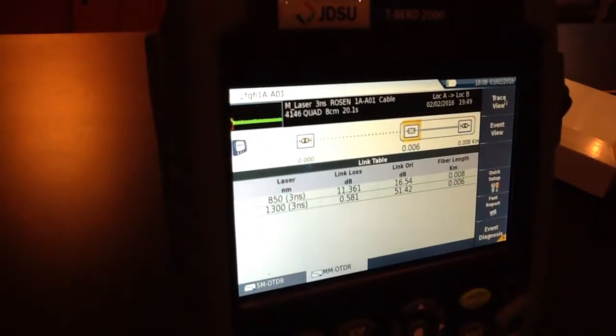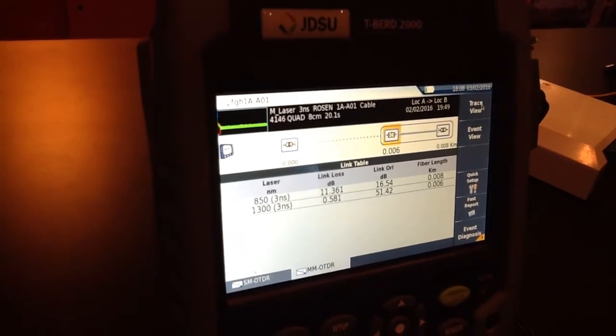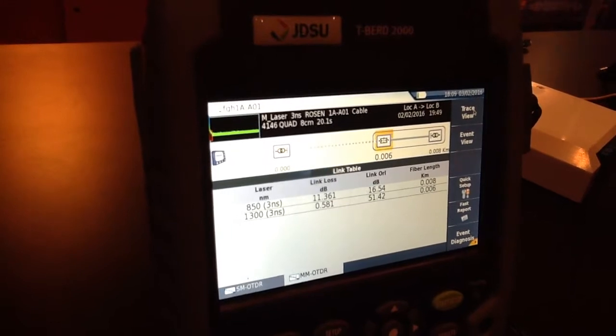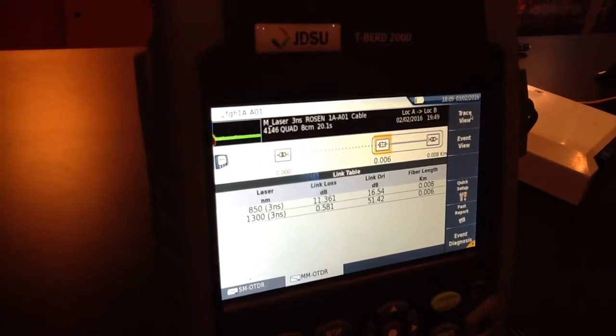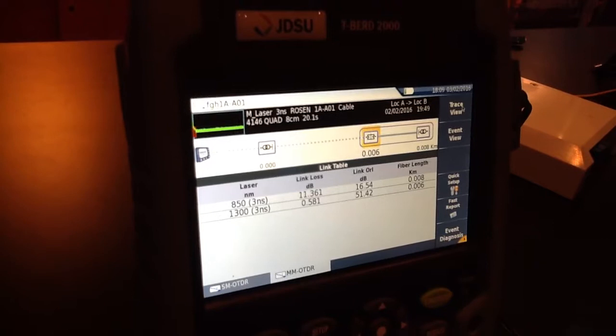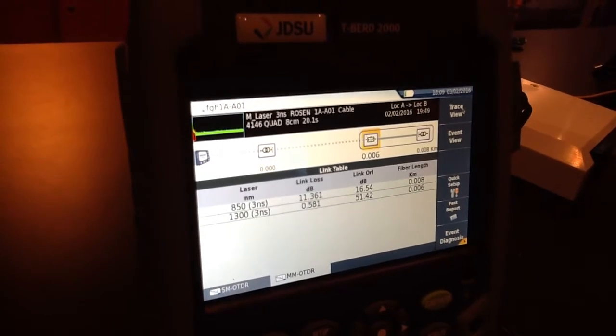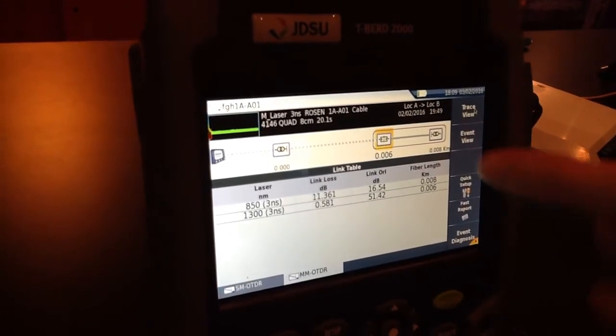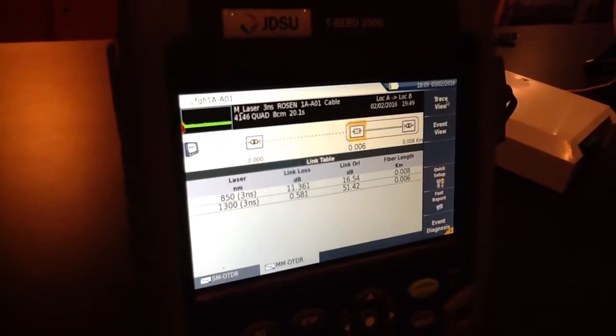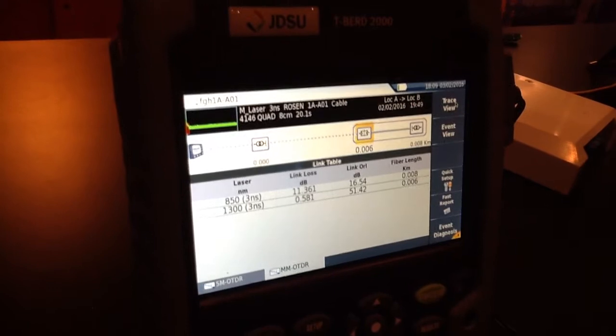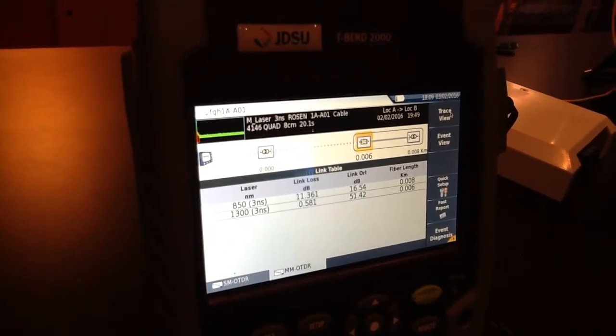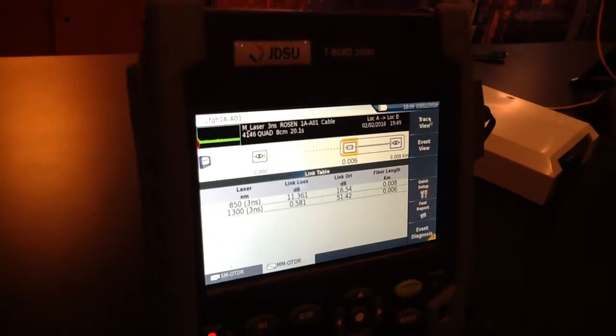In addition, I can switch over to a different view. This is called our SmartLink Mapper Schematic View. It gives you an icon-based view of what's actually going on. So rather than having to interpret all those different trace events, you can just see that at .006 kilometers away, that's where your connector is located — and here's the loss and reflectance happening at that point. This makes it a lot less intimidating for contractors out there and allows them to pull off Tier 2 certification.